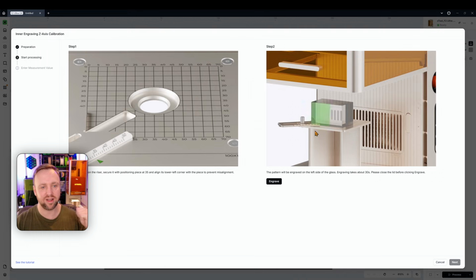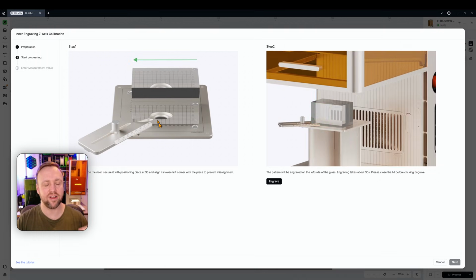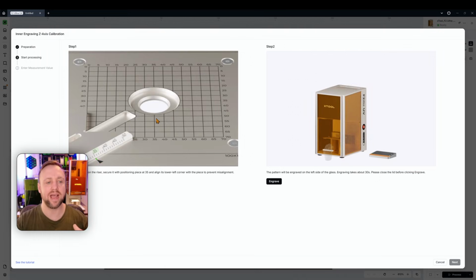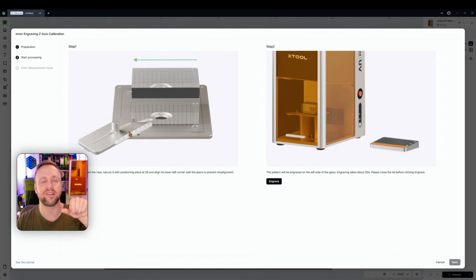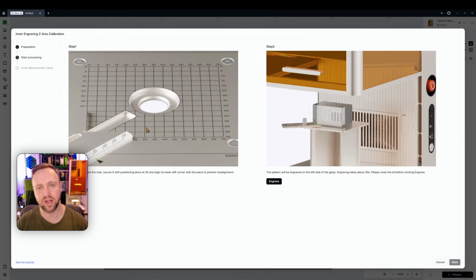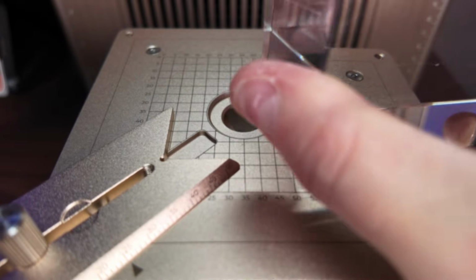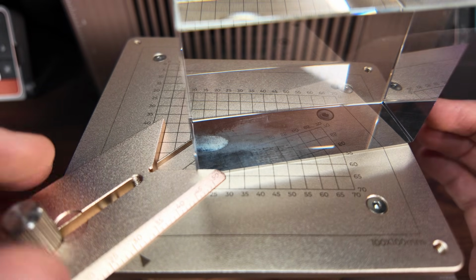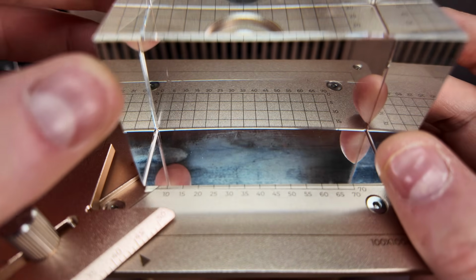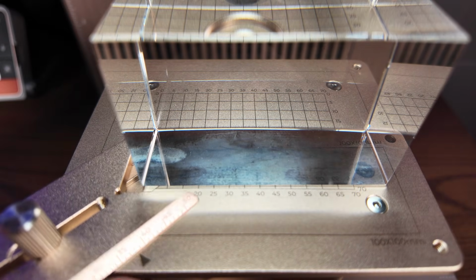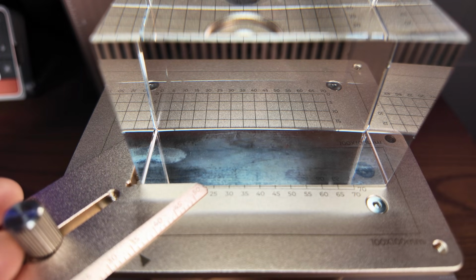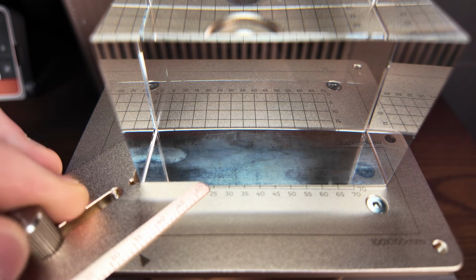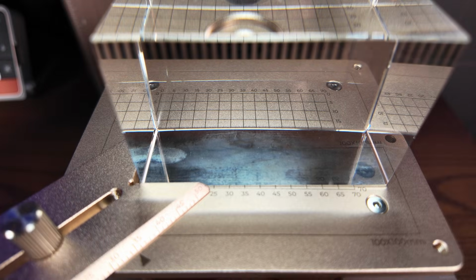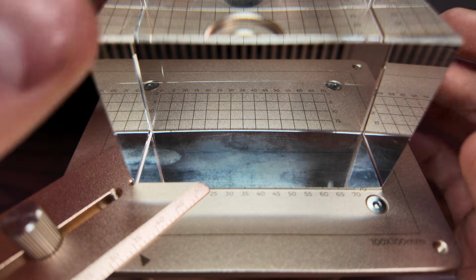and you can see the laser will start adjusting itself. It's going to ask us to place our crystal down and make sure the number on our slider that I showed you is down on 35. So we'll go ahead and do that now. We are going to place our crystal in. We're going to loosen this thumb screw off and just make sure there are numbers on the side here. You're probably struggling to see them, but we're going to make sure the 35 on this lines up with the arrow, and then we're going to tighten that thumb screw down. That is perfect. Then we are going to push our crystal into the corner.